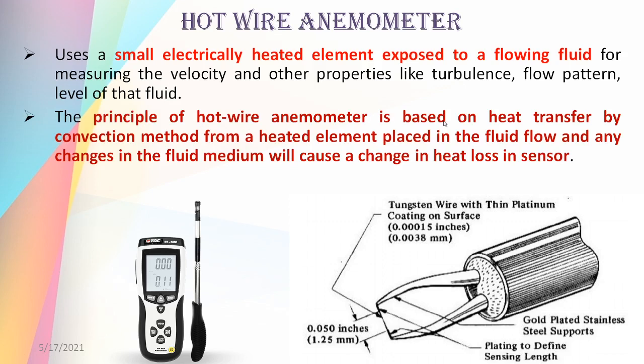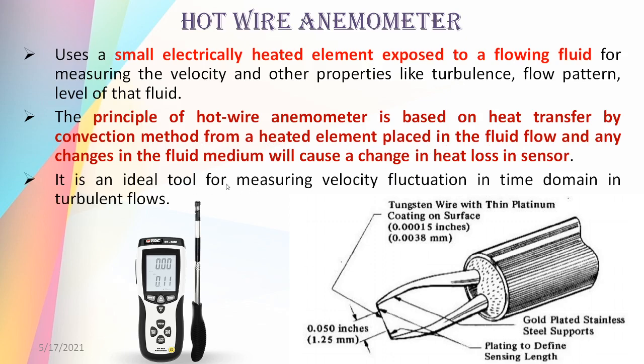The principle of the hot wire anemometer is based on heat transfer by convection method from a heated element which is placed in the fluid flow. Any changes in the fluid medium will cause a change in heat loss from the sensor. The heated element is placed in the flow, and the flow pattern and velocity cause heat to be transferred by the convection method. It is an ideal tool for measuring velocity fluctuations in the time domain in turbulent flows.